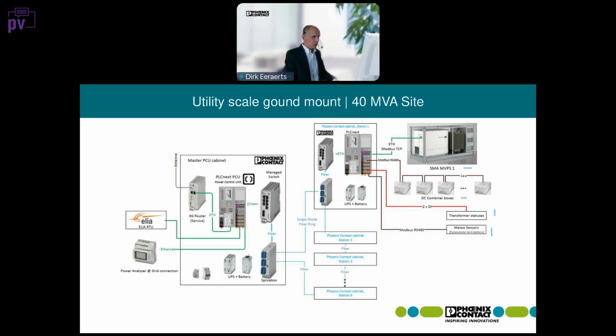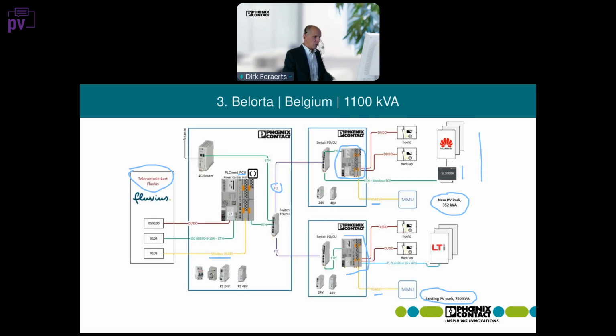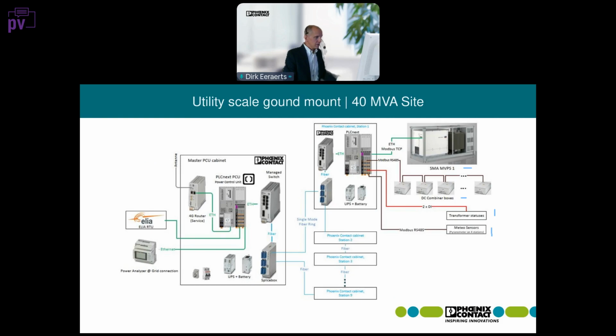Now, this is maybe a good time to talk also about commissioning. If I go back one slide, commissioning this type of plant would probably take you a day, maybe 2 days. But if we look at this scale of plant, 40 megawatt, utility scale, TSO connected, then we have a lot of other elements that come into play, a lot more tests to be done. And it's really at this level where certification can help us a lot in the commissioning. Without certification, you probably are looking at 3, 4, 5 weeks of commissioning tests. While if you can prove that a lot of the tests have been done before and are certified, you could move ahead a lot faster.